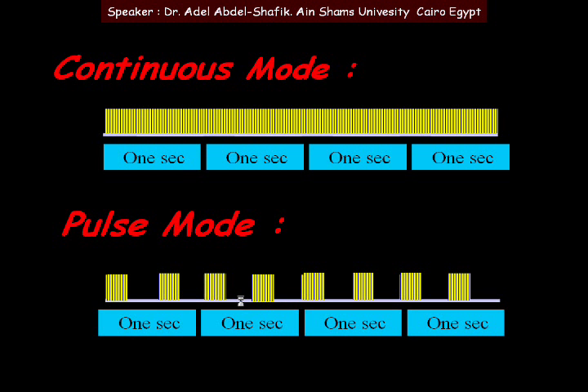In continuous phaco mode, the ultrasound is on all the time — every second is full with ultrasound. In pulse mode, we have part of the second with phaco on and another part with phaco off, so we get a lesser amount of energy.